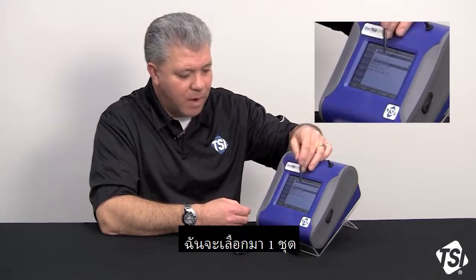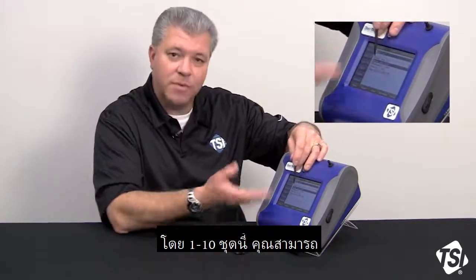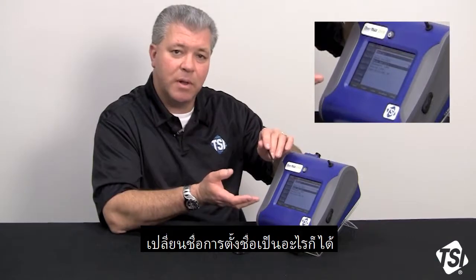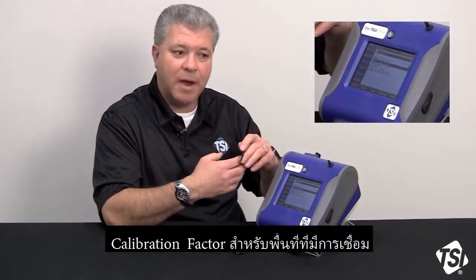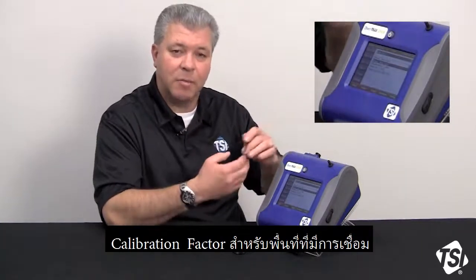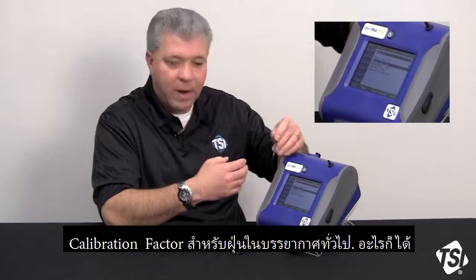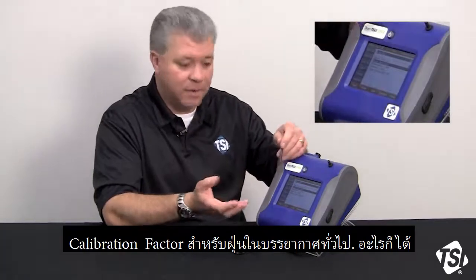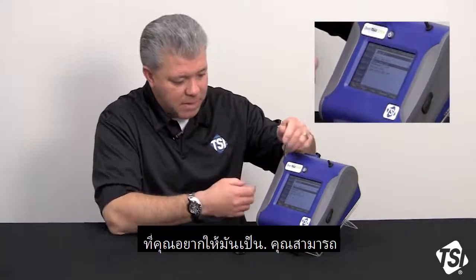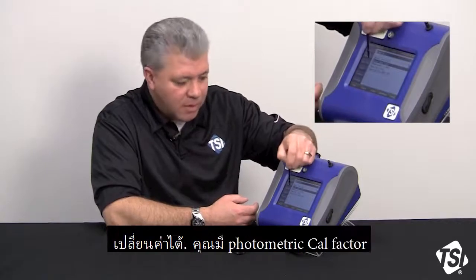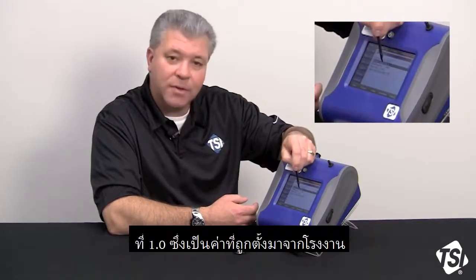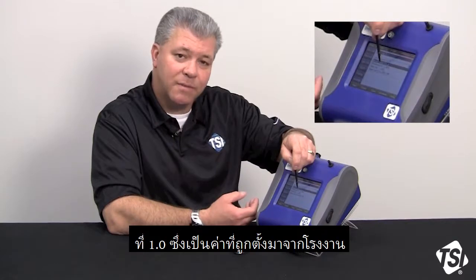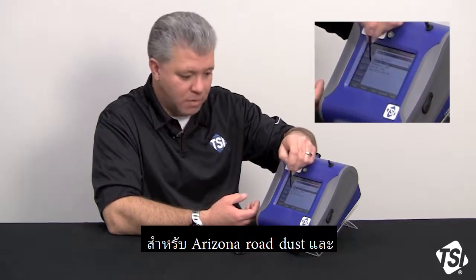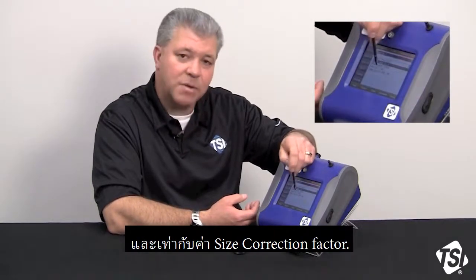I'm going to select one, and when it says test 1 through 10, you can change the nomenclature to be whatever you'd like it to be. A calibration factor for wood dust, for example. A calibration factor for welding fume. A calibration factor for ambient dust. Whatever you want that to be, you can go and change it. You have a photometric cal factor that's 1.0. That's the factory set point for Arizona road dust, and the same thing for size correction factor.